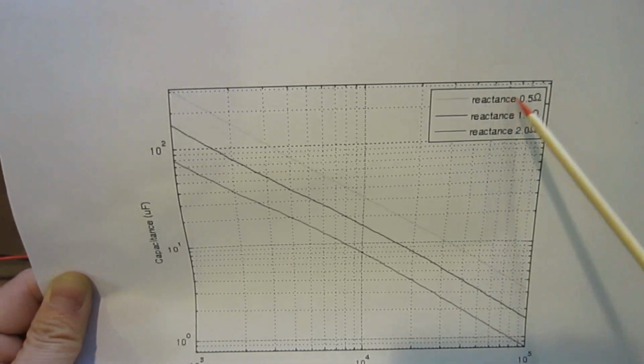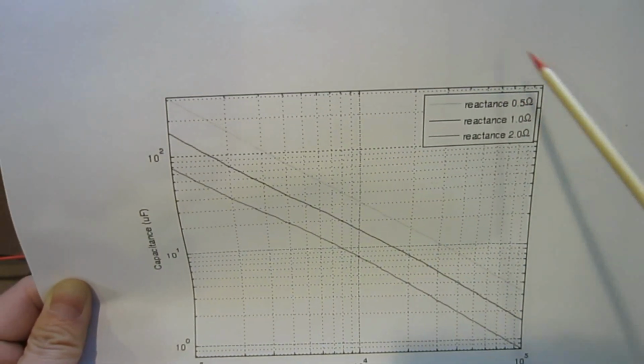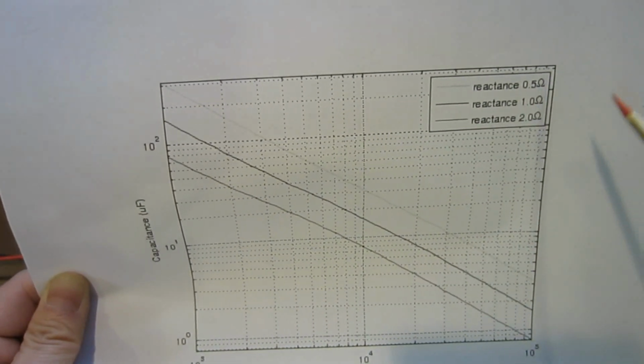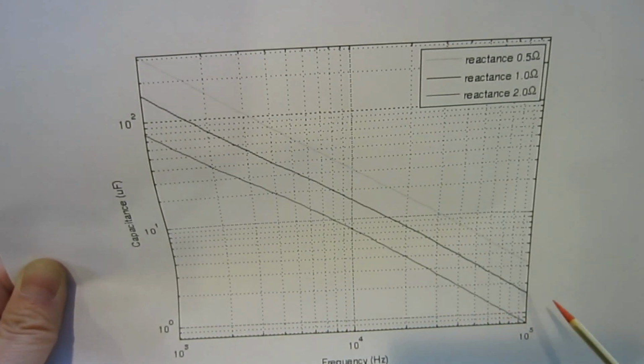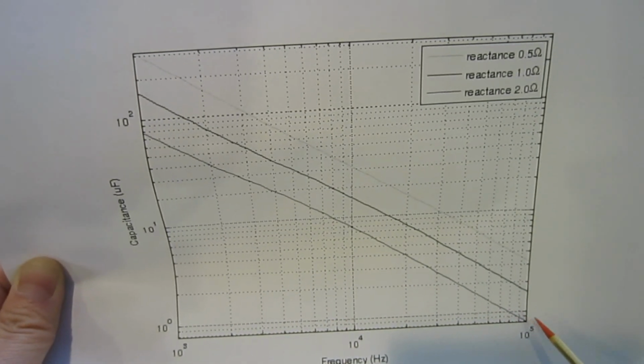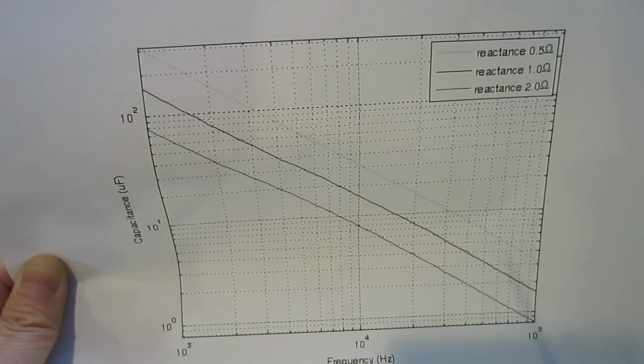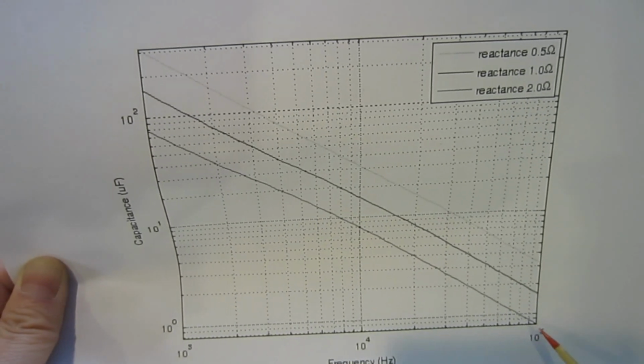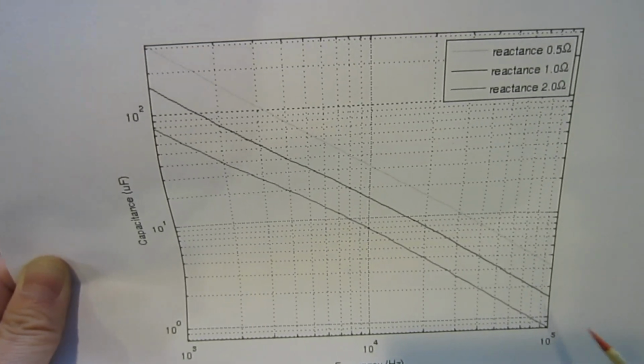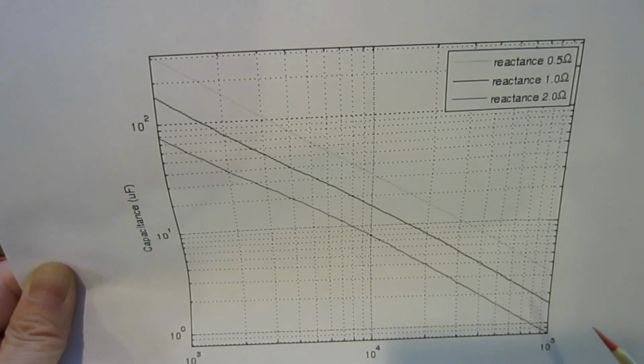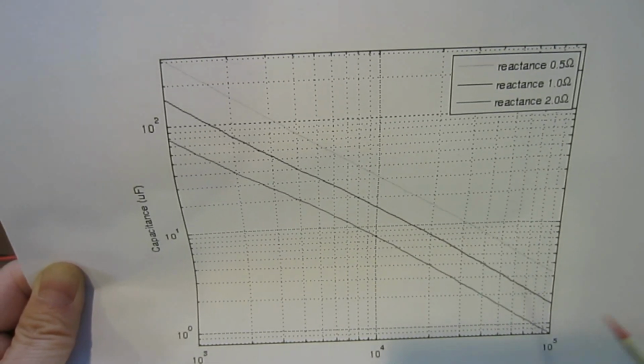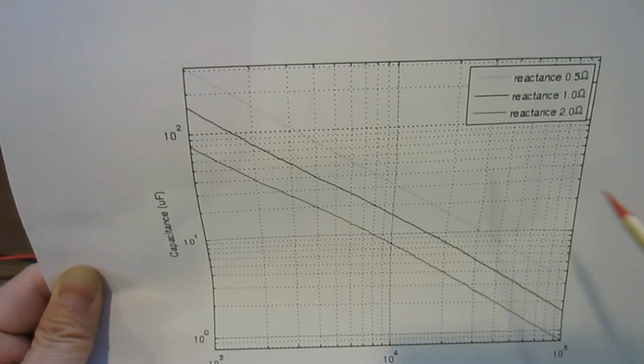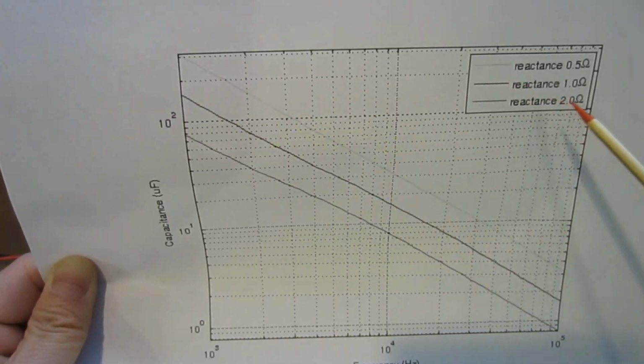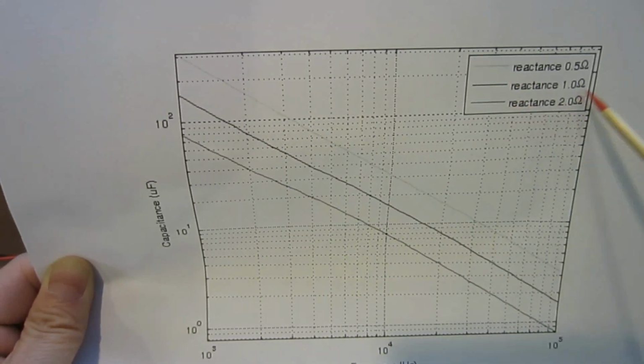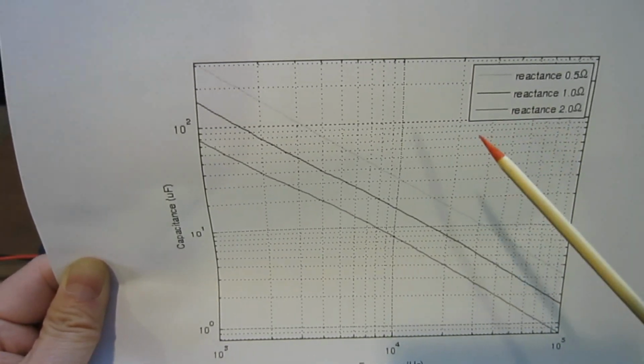But there are some technical reasons. Sometimes you can't go too high, because when you are increasing the frequency, you are introducing significant inductance in your measurement leads, which can also cause inaccuracy of your measurement. So we need to find a balance between the measurement frequency and the reactance that is acceptable for this measurement.